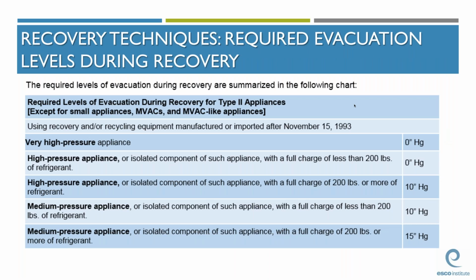This chart outlines the required levels of evacuation during recovery for type 2 appliances. Just as a reminder, although this was covered in earlier webinars, the pressure classification is now based on the refrigerant's liquid phase pressure at 104 degrees Fahrenheit. If you look at the pressure temperature chart that's supplied with the EPA prep manual, we highlighted the 104 degree line to make that more evident. So very high pressure refrigerants, such as R744, which is carbon dioxide, will have liquid phase pressures over 340 psig at a saturation temperature of 104 degrees Fahrenheit.